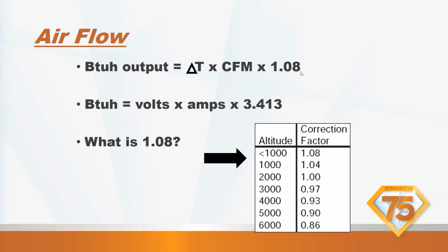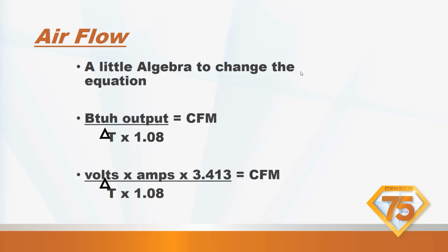Again, we already talked about the 1.08. That's the correction factor for specific gravity at different altitudes. We can change the equation a little bit using algebra, which we swore we never used when we were in high school, but we probably use it every day in our industry. So BTU output equals CFM times delta T times specific gravity, which means BTU output divided by delta T times the specific gravity equals CFM.